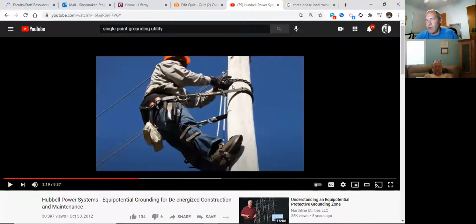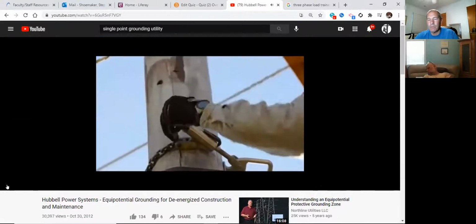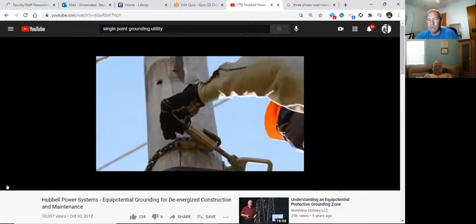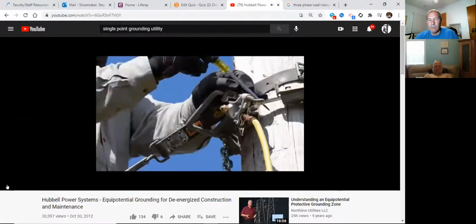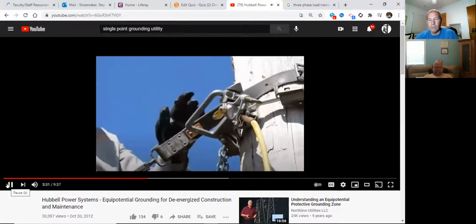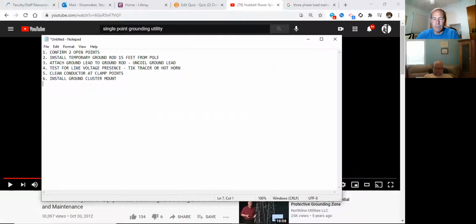When we go further on into the video here, you see a little bit of difference. They adjust that. So we'll show you that in just a moment. So install ground cluster mount. Exactly what it's saying. It's going to be a cluster of grounds once we attach all of them. A wheel tightener cinches the chain to secure the cluster bar in the best position. Now the free end of the cable attached to the ground rod comes up and is clamped tight on the bar. Okay, so next step. Install ground cable to cluster. That's the one coming from the ground rod up to the pole. And remember, it's uncoiled.